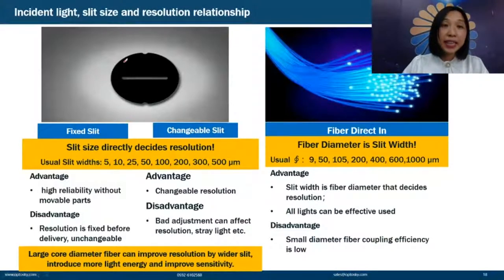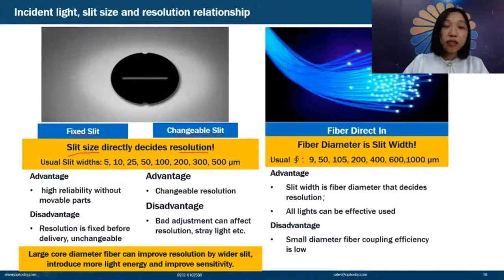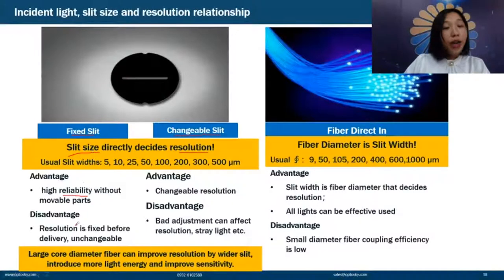Now let's discuss slit size and its relationship to resolution. There are two types: fixed slit and changeable slit. Slit size directly determines resolution. Common slit widths are 5, 10, 25, 50, 100, 200, 300, and 500 micrometers. Fixed slits have no movable parts so reliability is better, but the resolution is fixed at delivery and cannot be changed. Changeable slits allow the customer to adjust resolution for different applications, but improper adjustment can affect resolution and stray light performance.